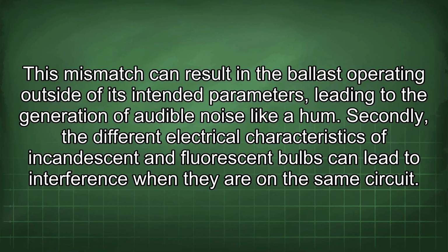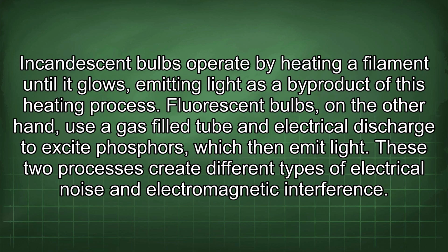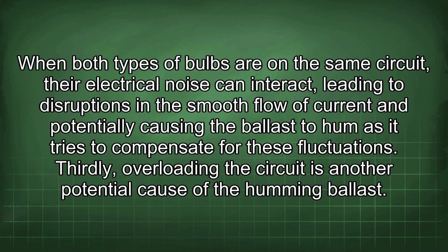This mismatch can result in the ballast operating outside of its intended parameters, leading to the generation of audible noise like a hum. Secondly, the different electrical characteristics of incandescent and fluorescent bulbs can lead to interference when they are in the same circuit. Incandescent bulbs operate by heating a filament until it glows, emitting light as a byproduct of this heating process. Fluorescent bulbs, on the other hand, use a gas-filled tube and electrical discharge to excite phosphors, which then emit light. These two processes create different types of electrical noise and electromagnetic interference. When both types of bulbs are on the same circuit, the electrical noise can interact, leading to disruptions in the smooth flow of current and potentially causing the ballast to hum as it tries to compensate for these fluctuations.